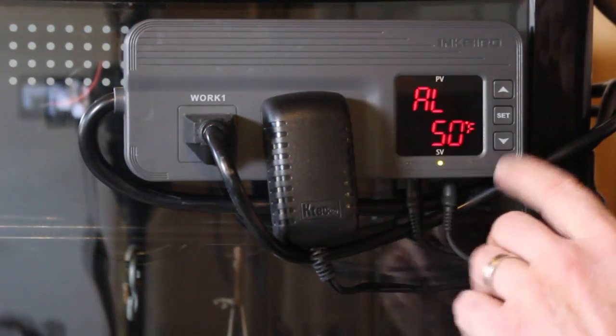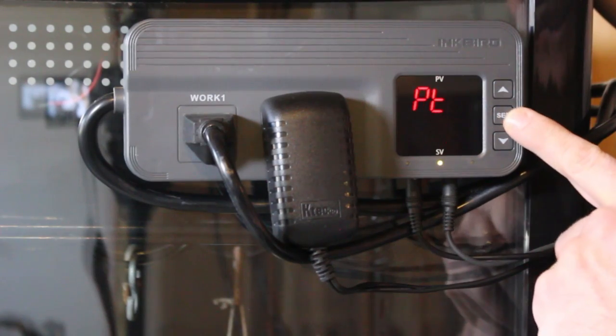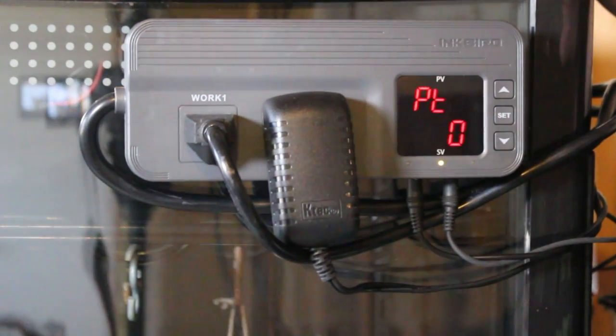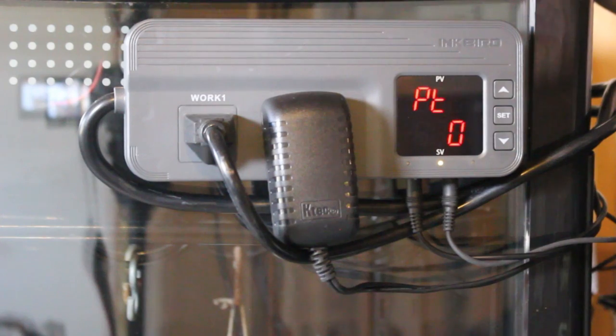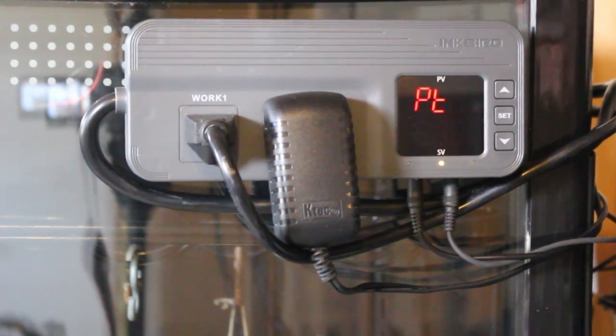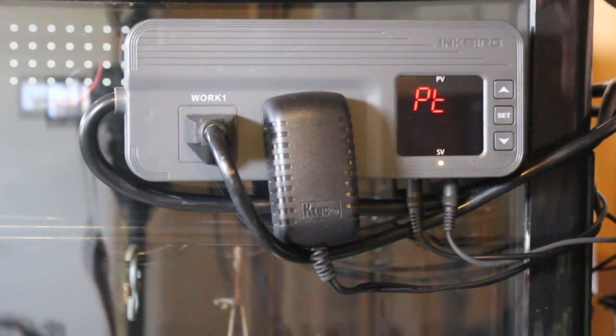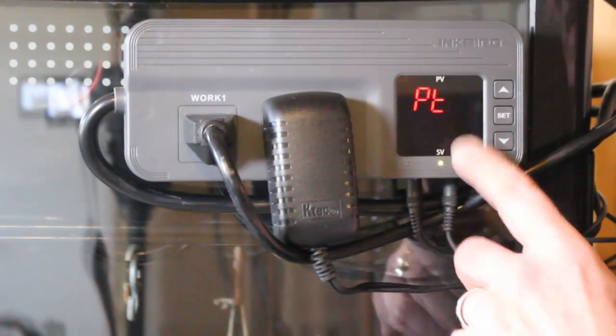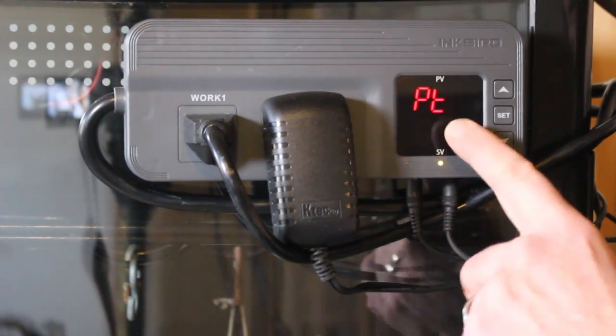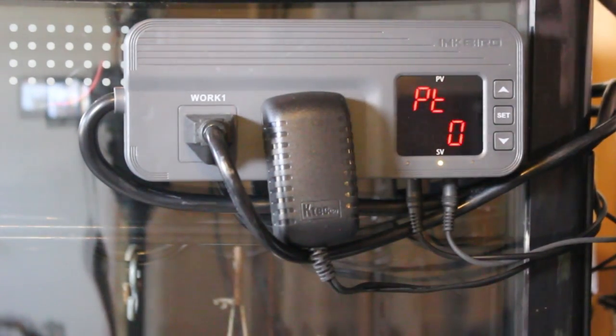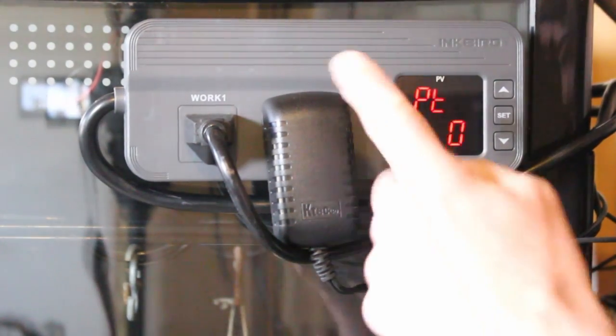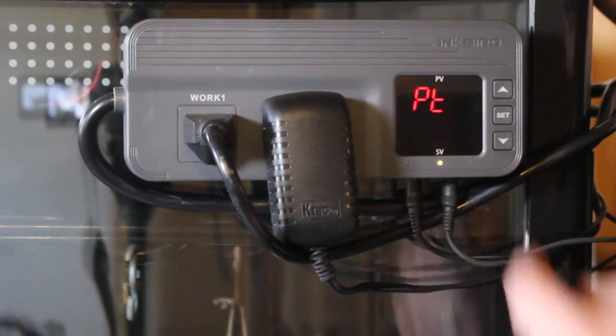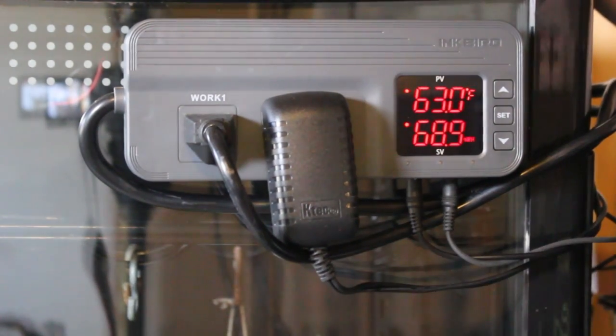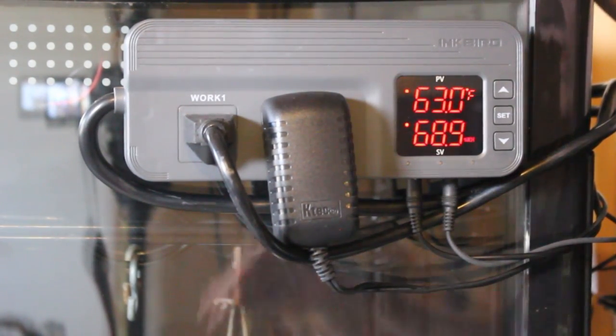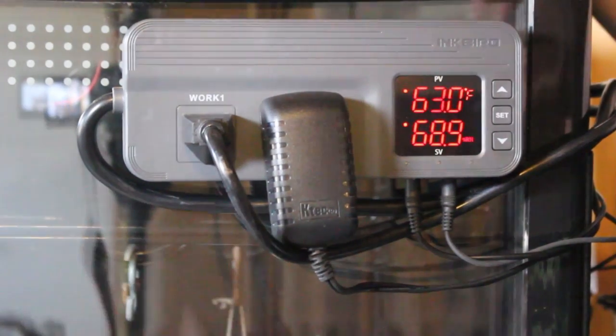That's kind of my window of goodness versus alarm condition. PT is compressor delay. Essentially, if you've got a different kind of cooling arrangement or some different equipment other than a fridge where you want to control it by temperature, but maybe the way your cooling equipment works is that a compressor comes on. So you can set this from 0 to 10 minutes of time, meaning that I've got it set to 0 right now because I'm just using the temperature differential. If you want to use the compressor time setting, you can set it to go ahead and wait a certain amount of time, from 0 to 10 minutes.